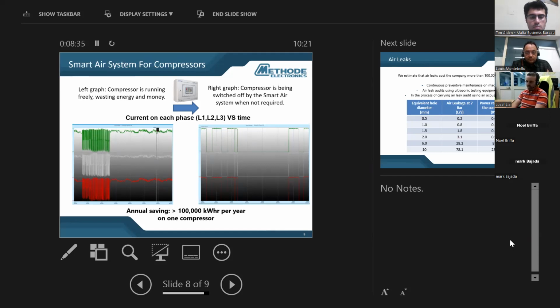With the system, we calculate that we have seen a saving of around 100,000 kilowatt hours per year per compressor, which is quite significant for us. With the system, we see the left-hand graph. This shows the current on each phase versus time. During low periods, the compressor is running freely, and on the right-hand side, during those periods, the compressor is switched off completely, generating zero current, and is only working when required.